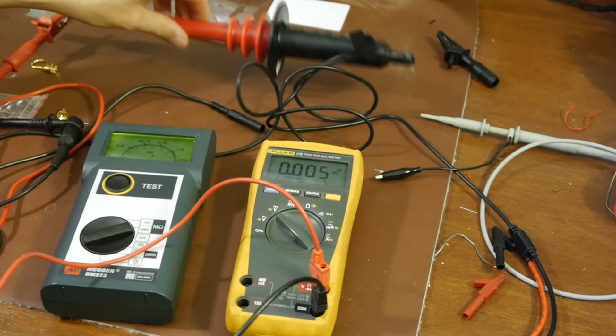The basic accuracy of the fluke meter without the probe is obviously going to be better than having this attenuator in circuit. So what we'll do is risk my wonderful fluke meter by plugging it directly into the insulation resistance meter, but on the 500 volt range. Let's try that. Got it plugged in right, it's reading a residual 4 volts at the moment. I don't know if this is a good idea, but I wanted a new fluke meter anyway, so let's try.